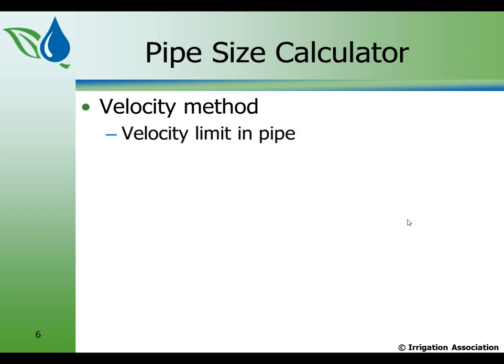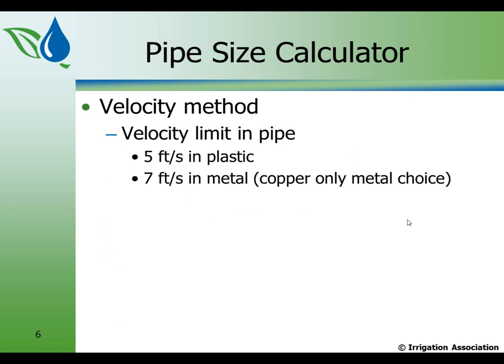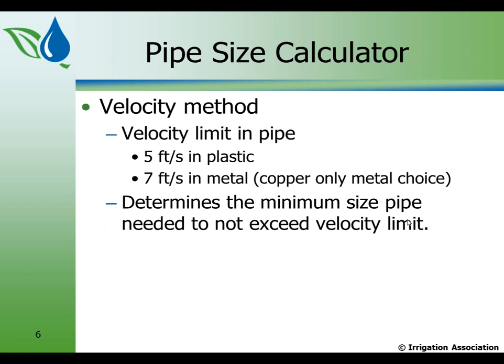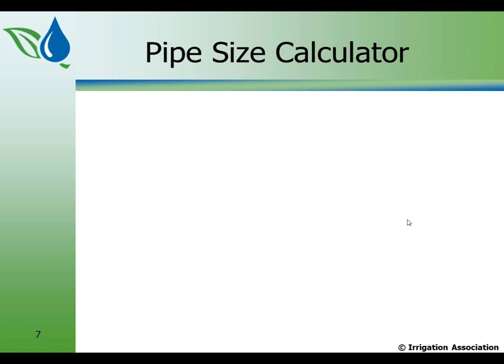In the velocity method, there is a velocity limit in pipes, and the velocity limits are derived based on the potential effects of water hammer. And water hammer is the phenomenon that occurs when you rapidly stop water, usually as a result of closing a valve too quickly. And it can damage or burst the pipe. The generally accepted numbers are 5 feet per second in plastic and 7 feet per second in metal. However, in this size calculator, we're only using copper as the only metal choice. It determines the minimum size pipe needed to not exceed the velocity limit.